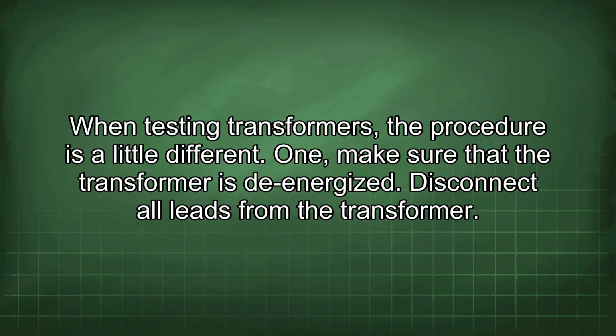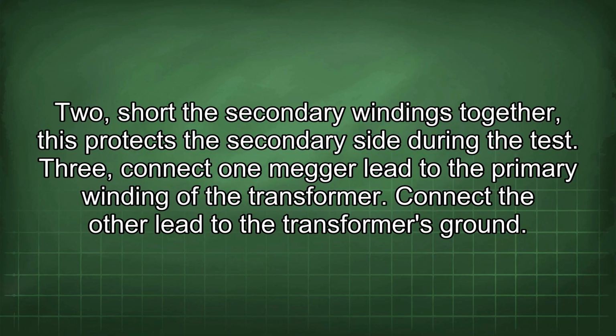When testing transformers, the procedure is a little different. 1. Make sure that the transformer is de-energized. Disconnect all leads from the transformer. 2. Short the secondary windings together. This protects the secondary side during the test. 3. Connect one Megger lead to the primary winding of the transformer. Connect the other lead to the transformer's ground.